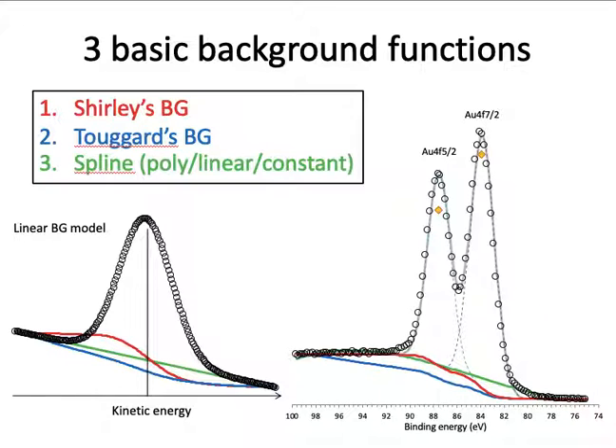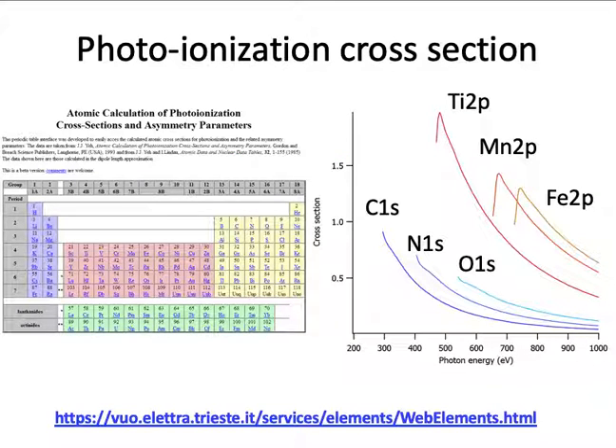There are three basic background functions well-known in XPS. When you quantify atomic elements in your sample, you need to know the sensitivity factor for each atomic element and each orbital — this is the photo-ionization cross-section database, available online. Standard lab XPS uses well-known sensitivity factors; however, at a beamline you can vary the photon energy to measure XPS spectra, and the sensitivity factor also depends on the photon energy, so you must normalize the sensitivity factor for each XPS spectrum.